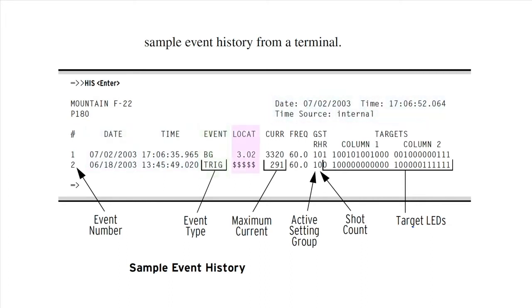type, fault location, recloser shot count at the start of the event report, system frequency at the start of the event report, front panel fault targets at the time of trip, phase IA, IB, IC, ground, and negative sequence current magnitudes in amps primary measured at the largest phase current magnitude in the triggered event report. The recloser control includes the event summary in the standard event report.